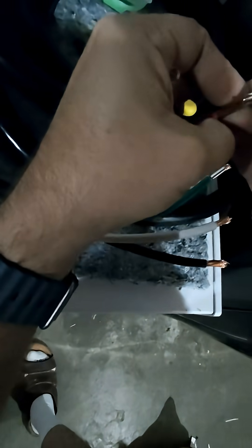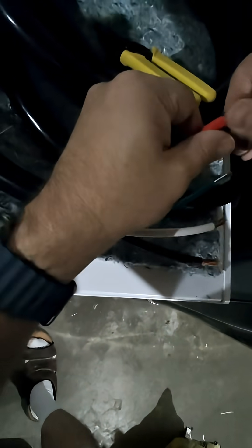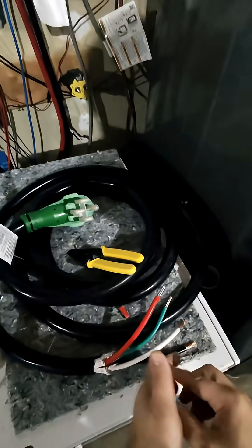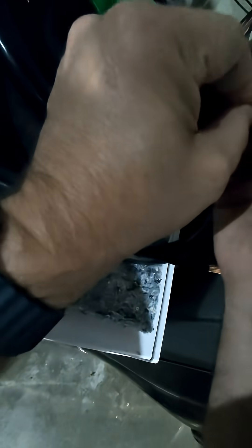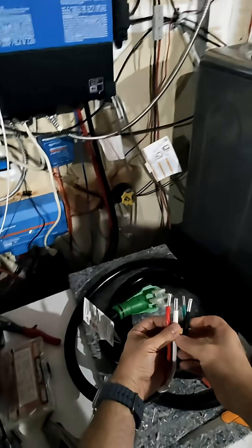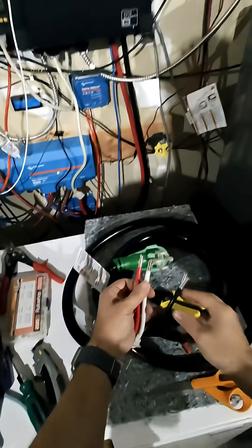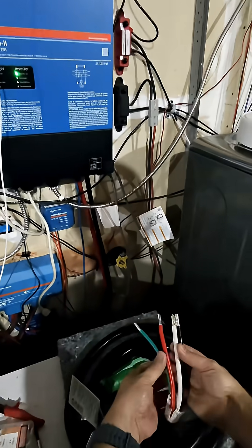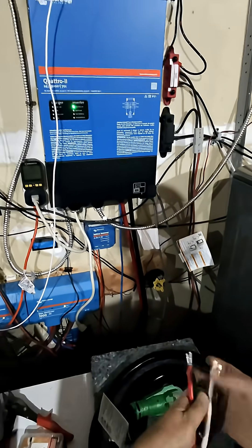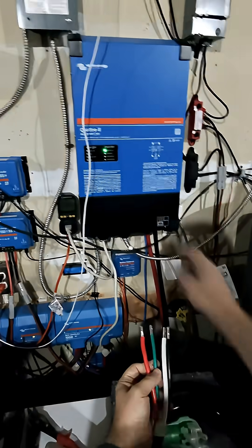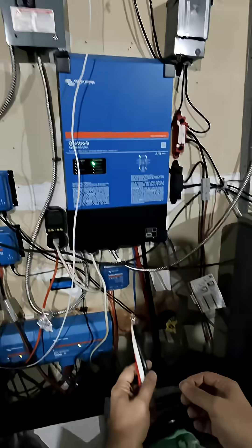The whole purpose of this is to make it so that the fine wire doesn't work loose over time from thermal cycles and whatnot, which would create a hazard, even if it works initially. Okay, I've got the ferrules on, but I have not crimped them yet. Okay, now these are crimped. I've also trimmed a little bit off excess. These are ready to go in and be forcibly screwed into these screw terminals.